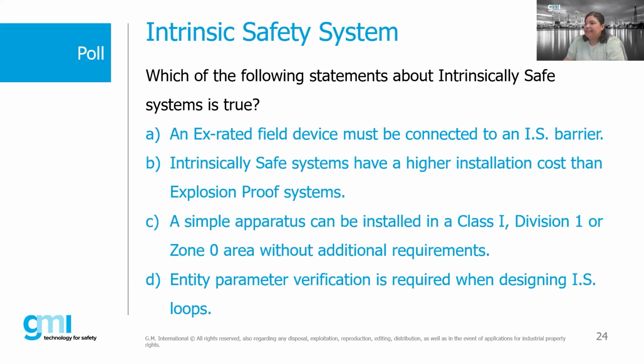Good job, everyone. It was kind of tricky, and I do want to spend some time on this one. So the right answer was D. Entity parameter verification is required when designing IS loops. That's always true. The first one, an EX-rated field device must be connected to an IS barrier. An EX-rated field device can be an explosion-proof field device, can be a non-arcing field device, can be an increased safety field device, right? We said the field device has to be intrinsically safe rated. So that's important to keep in mind, and that's one of the misunderstandings or confusions that sometimes we see in the field. Well, good job, everyone.